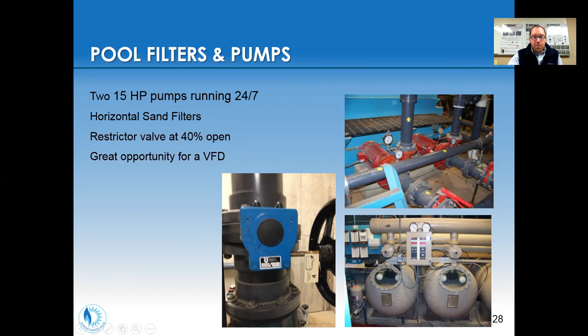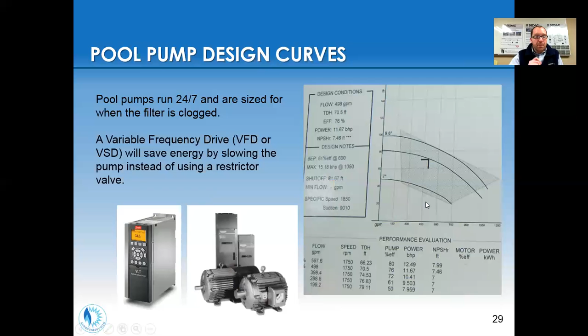But a better way to do that would be with a variable frequency drive. A variable frequency drive, sometimes called a variable speed drive, reduces the frequency of the power going to the motor, and reduces the energy by a square. So it really is an enormous energy reduction by reducing the speed of the motor, and it can still fall within the design parameters of the pool pump and the gallons per minute of the system.